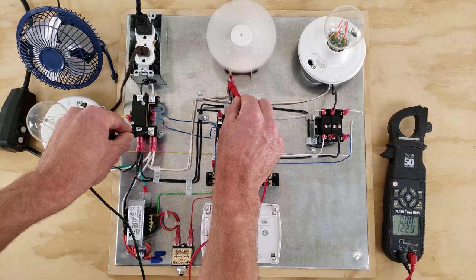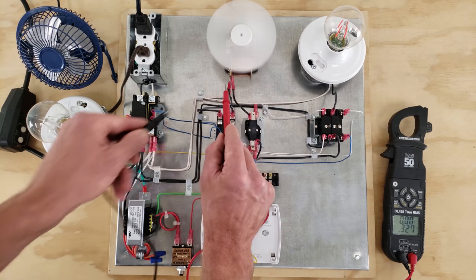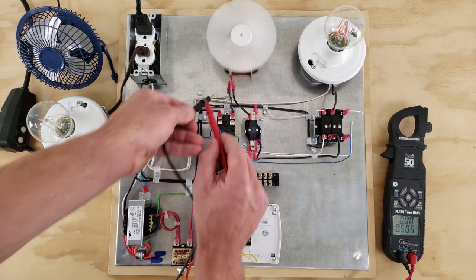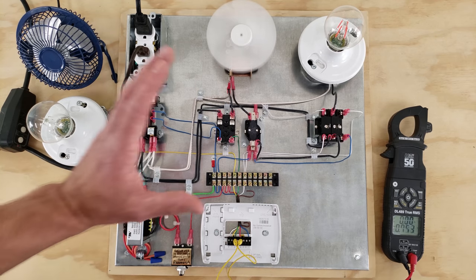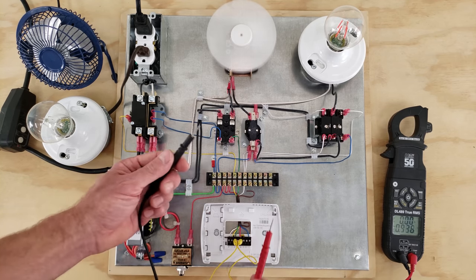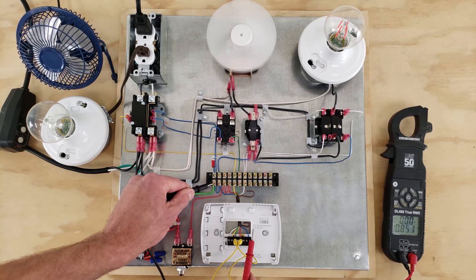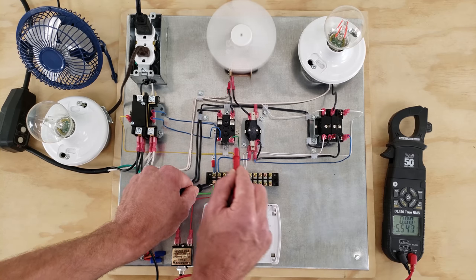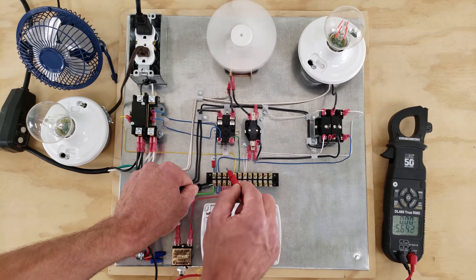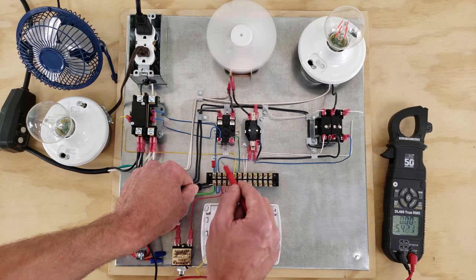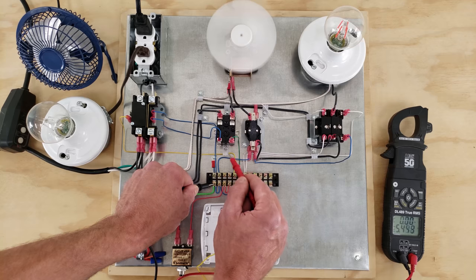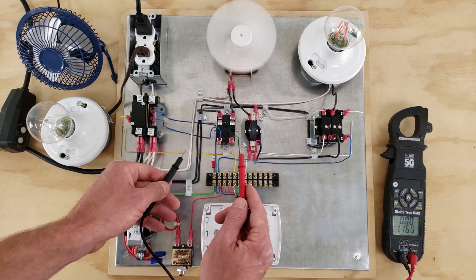So we do have 120 here and we have our common over there. So we could measure 120 volts right there. So that's how you troubleshoot. You want to place one probe on your common for your 24 volts, and then you're just moving the other around to see where you're losing your electrical circuit, where it's open. And when it's open, you no longer have voltage, and that's where your problem is.